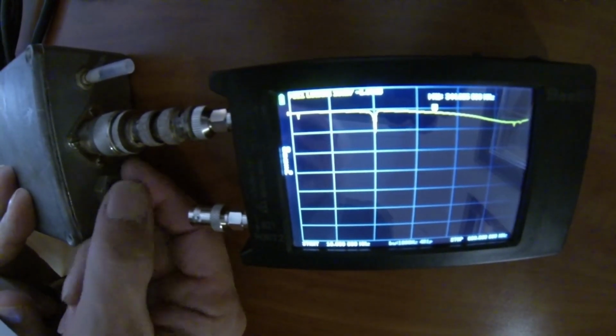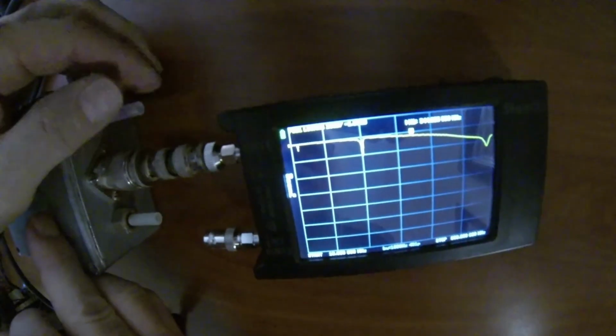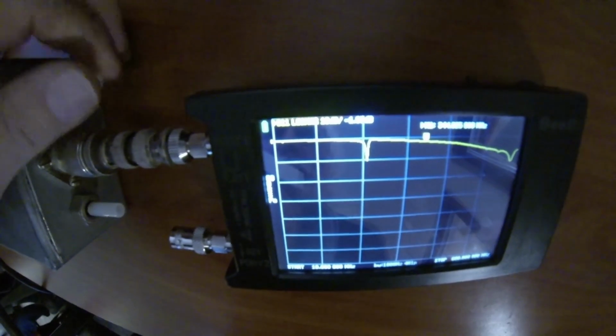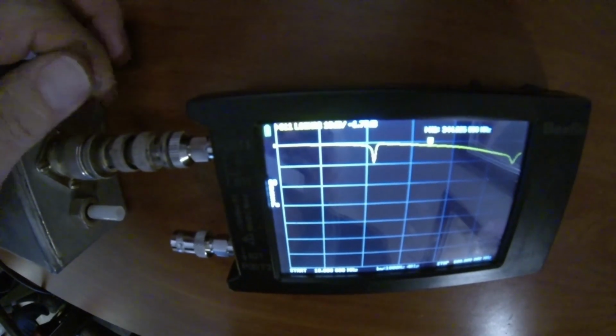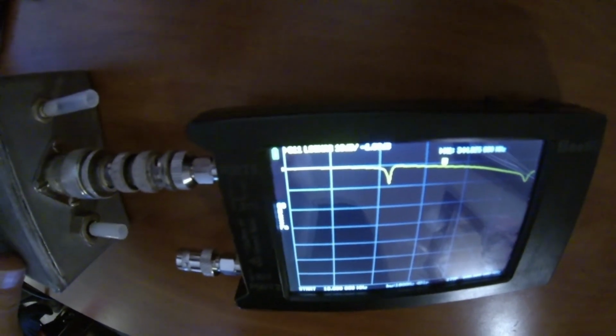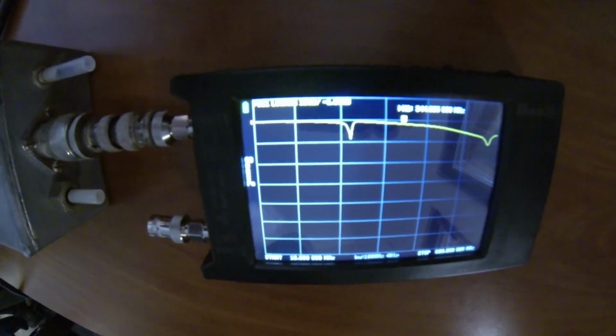What we can do with this here is adjust the tuning by rotating these piston capacitors. So I rotate this one here, and we're changing the frequency. And you see the dip is shallower, so it's not as good a match. What you need is for the dip to be at the frequency you're interested in, and it's got to be low.